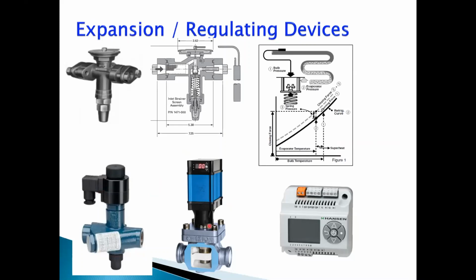Whereas the motorized valves, which are the so-called step motor valves, are used for bigger plants and bigger operations. Bigger capacity valves are available. They have a step motor on the top, and it is connected to your electronic controller, which again senses the temperature difference across the evaporator. Many controllers can also use the pressure and temperature at the outlet of the evaporator. It depends on your requirement, and depending on the superheat, it opens and closes this motorized valve. This gives you fine control of the superheat.